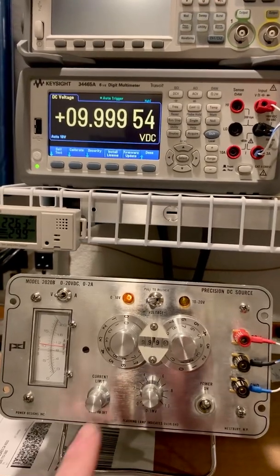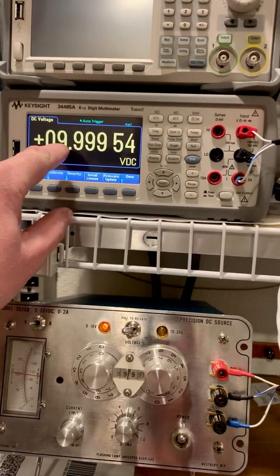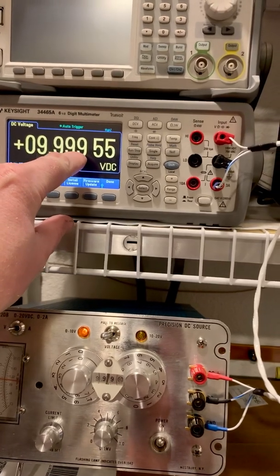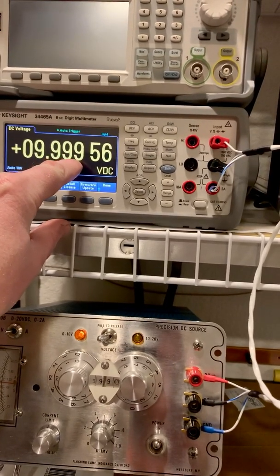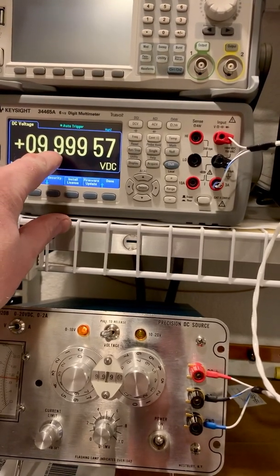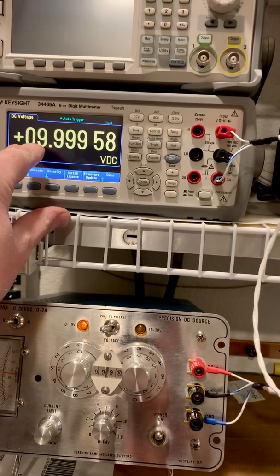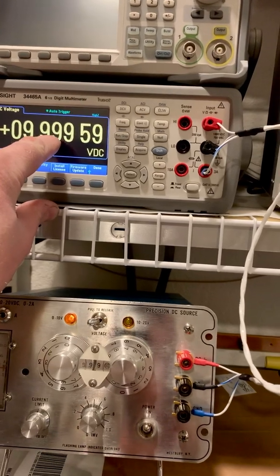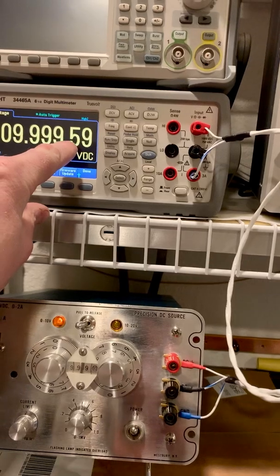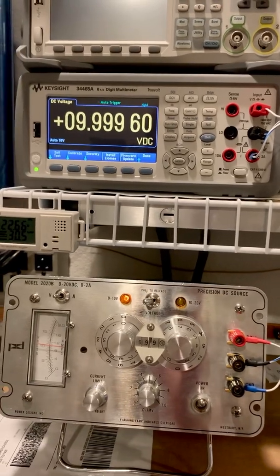The set calibration is spec'd at 0.1%. That would be 1%, 0.1%, 0.01%. 0.004% is where it's at right now, not too bad.